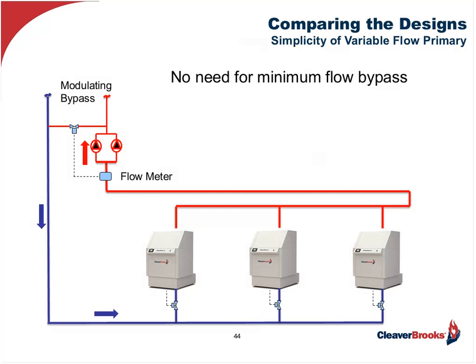Now, one thing I sometimes see in the field is people want to try and maintain minimum flow through the boilers, and they add a modulating bypass and a flow meter.